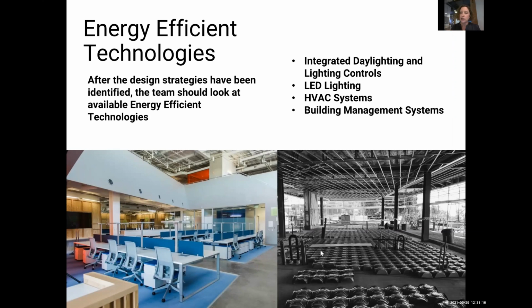The project on the lower right is a high-end residence we're working on, where we used an air floor system, similar to a radiant heat system in the floor, but with air. You're moving heated or cooled air through metal domes installed under the concrete in the floor, giving about 6 inches to the HVAC system in the floor. The air is heated and cooled, which transmits through the concrete slab on top, in turn heating and cooling the space right next to the occupants.